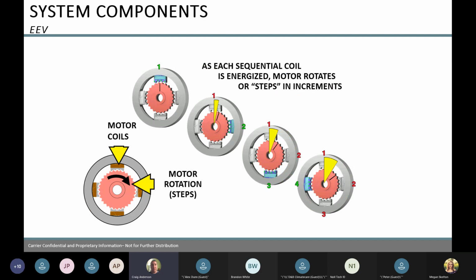So this is kind of what your EE valve looks like. It monitors the refrigerant flow going into your indoor unit. It moves in increments or steps, as some of the guys say, and it can have up to 480 steps. So this valve is opening and closing based on what the return air temperature and the coil temperature sensor are telling it the compressor and outdoor unit need to do.